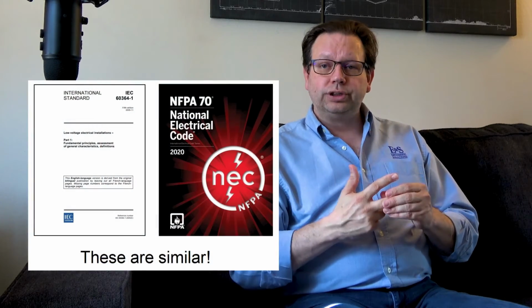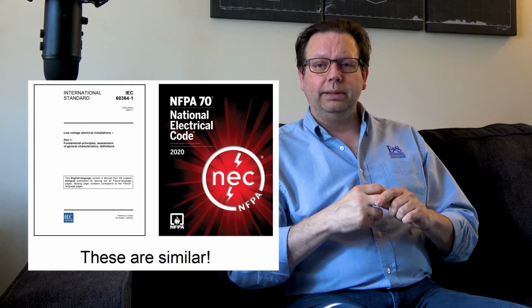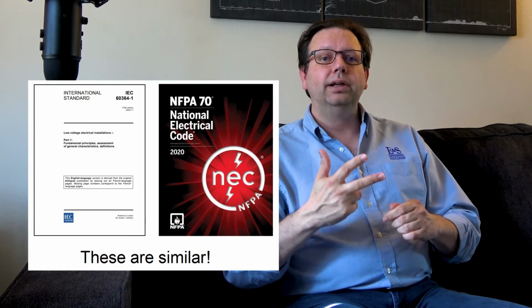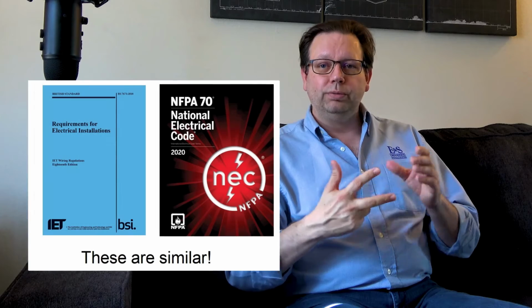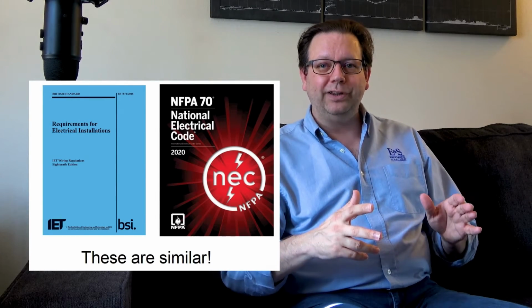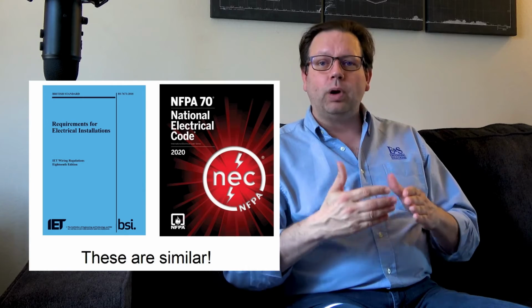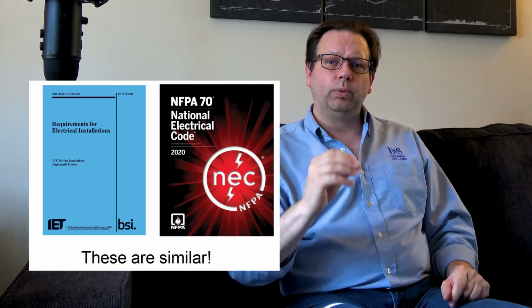In the grounding business, in the National Electrical Code, we use the word grounding. They use the word earthing. If you search the National Electrical Code, you'll never see the word earthing anywhere in it. Same thing in the British Code—if you look up the word grounding, you'll never see it anywhere in there. They're completely swappable, though. In most cases, you can swap the word earthing and grounding—they mean the same thing. Both documents have requirements for below-grade grounding and above-grade grounding, and again, they tend to be far more similar.